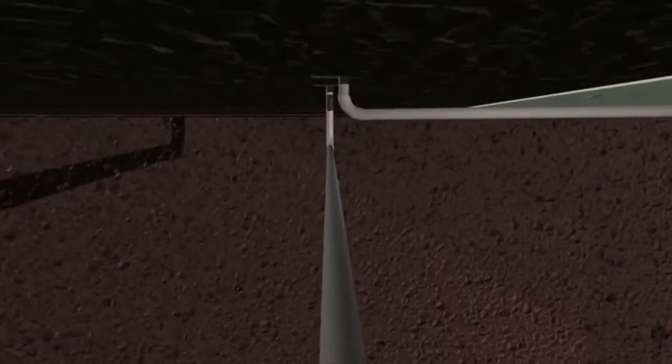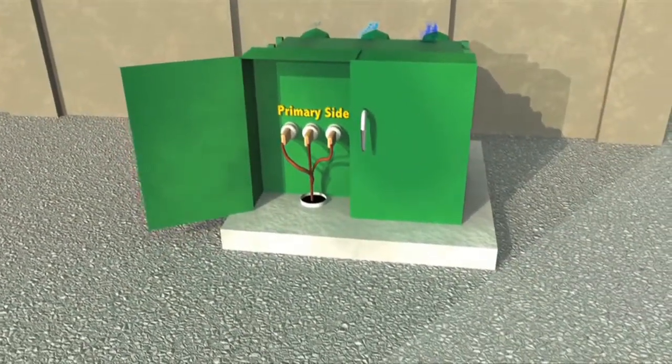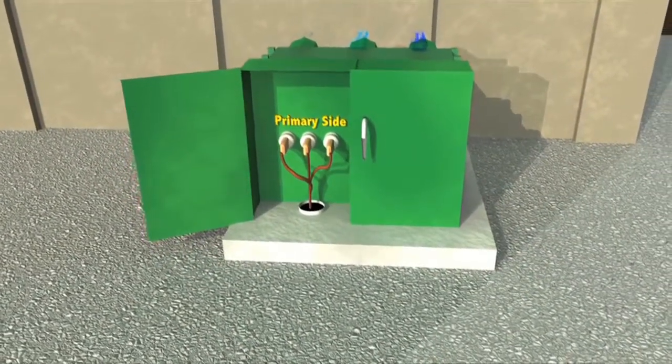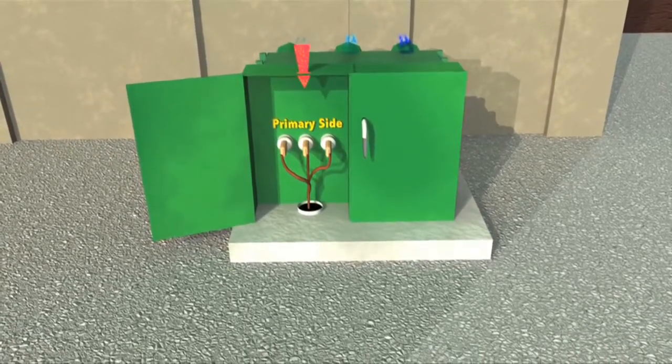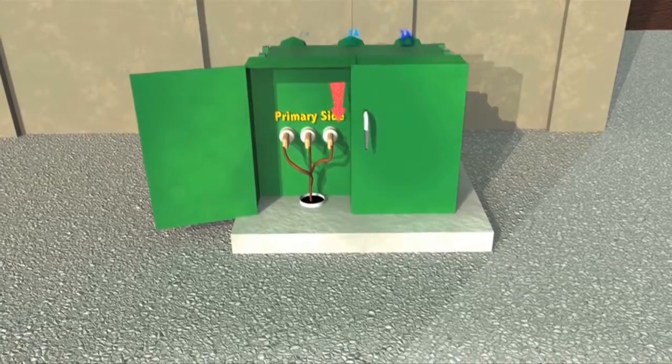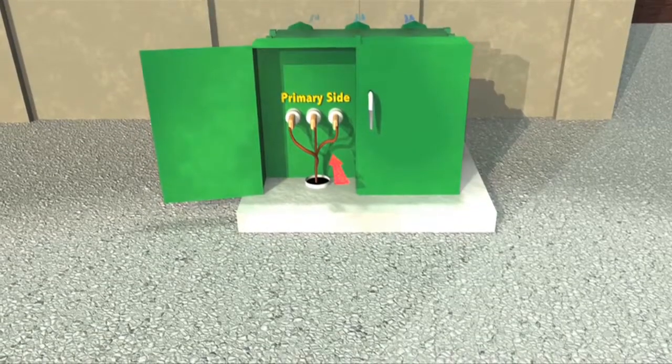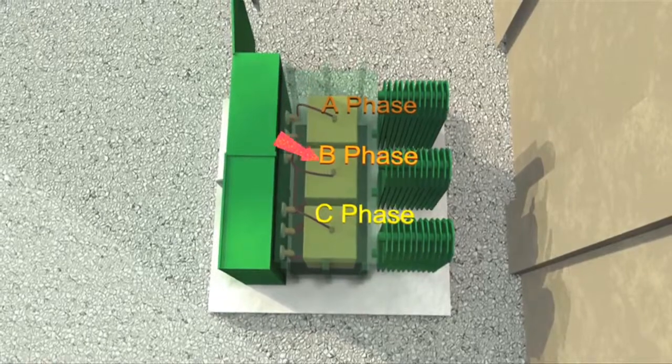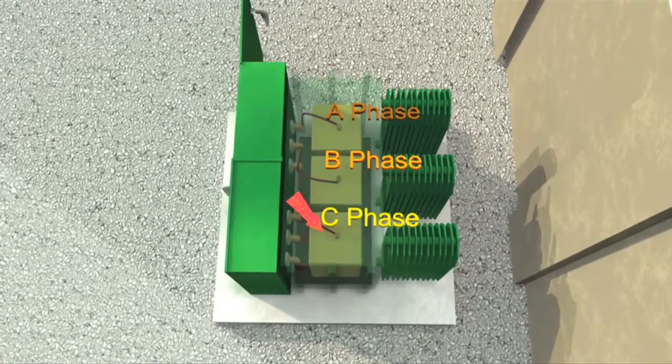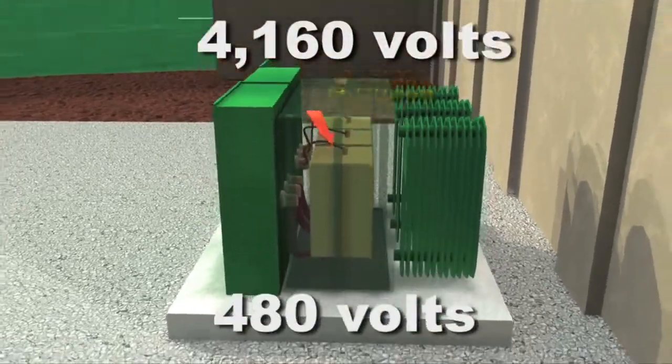This conduit travels underground and enters the oil transformer on the high or primary side of its junction box. Let's look at how the oil transformer works. The junction box receives the incoming power on the high or primary side. It enters the transformer through insulated copper connectors. Notice there are three wires. This is our three-phase system. There are three windings, one for each of the wires or phases. The wires are connected to the top of the windings. The windings in this transformer will step down the voltage to 480 volts.